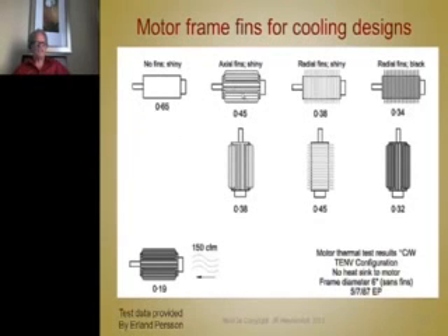Now, axial fins like that, this is all natural convection. So it drops to 45, but if you mount the fins the other way, it drops to 38. But if they're black, it drops to 34. Here, if they're vertical, it's 0.38. If you use the concentric fins but mount it vertical, it goes up. But if you paint it black, it goes back down again. So this is some very important data, and you can use these relative numbers and apply these percentages to any of your machines. It's very useful, real data.